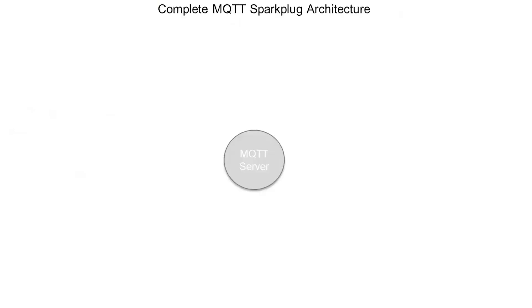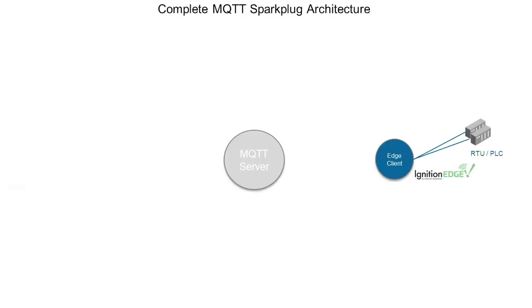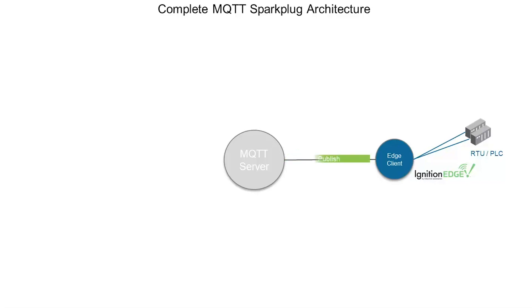Looking at our architecture now with Sparkplug, we still have our central MQTT server infrastructure and MQTT clients at the edge. If this was Ignition Edge connected to PLCs, RTUs, and flow computers, we could establish our connection, connect into our MQTT server, subscribe to information we're interested in, and start publishing all of those process variables using Sparkplug.